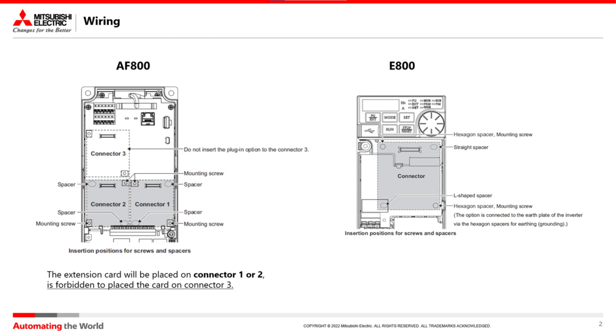The FR-A8AP encoder board can be mounted on the AF-800 inverter or on the E800 inverter. If an AF-800 inverter is used, the encoder board must be mounted in connectors 1 or 2. It is forbidden to mount it in connector 3.